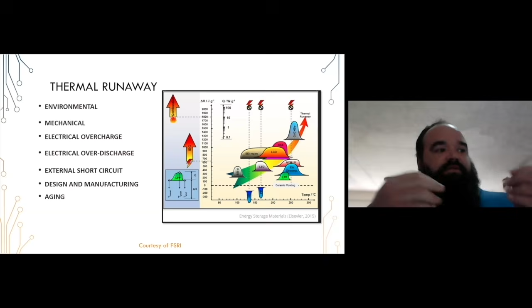Okay, design and manufacturing. So if there's a poor design - a lot of your cheaper types of batteries and manually manufactured batteries have nuts, bolts, and all of these type of things that you would typically find come loose with age, etc., or they're not tightened correctly, or they're not torqued, spec'd, etc. within realm. They work for just a set time, but they do need to be maintained. A lot of the cheaper batteries do have a bolt and nut configuration when doing their arrangements.